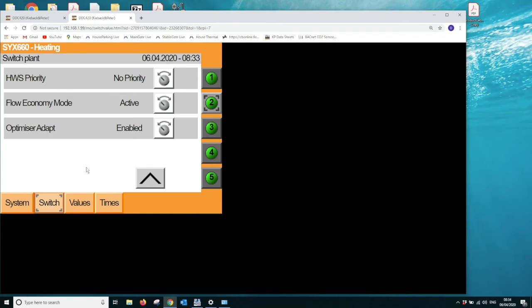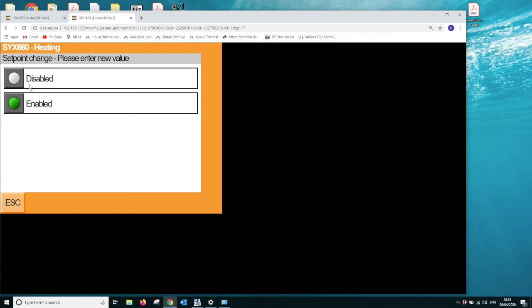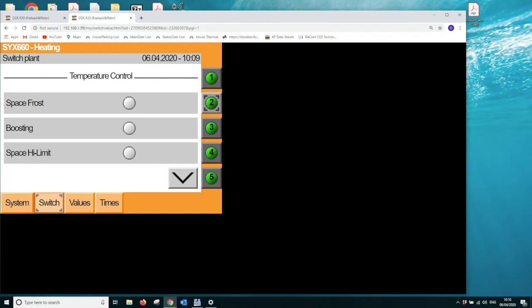So we have the ability here to identify what the problem is for the long warm-up time. During that time, where the warming up is taking a very long time and we want to understand why, it might be advantageous to disable the optimizer adaptation, and we hold it as a fixed rate until we identify what the problem is. We can disable the adaptation by clicking on disabled on this screen. Okay, so that's the heating menu now set up with its main functions.